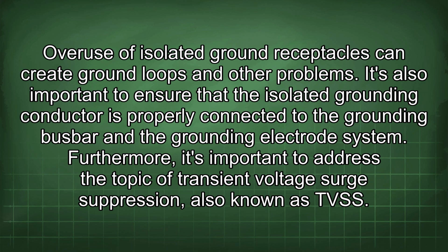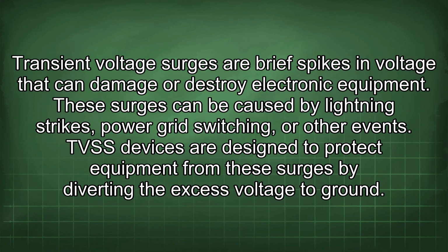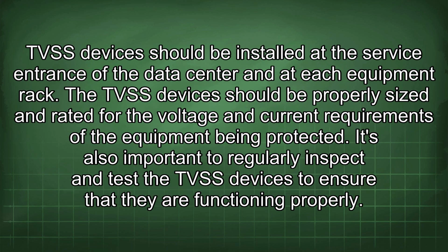Furthermore, it's important to address the topic of transient voltage surge suppression, also known as TVSS. Transient voltage surges are brief spikes in voltage that can damage or destroy electronic equipment. These surges can be caused by lightning strikes, power grid switching, or other events. TVSS devices are designed to protect equipment from these surges by diverting the excess voltage to ground. TVSS devices should be installed at the service entrance of the data center and at each equipment rack. The TVSS devices should be properly sized and rated for the voltage and current requirements of the equipment being protected. It's also important to regularly inspect and test the TVSS devices to ensure that they are functioning properly.